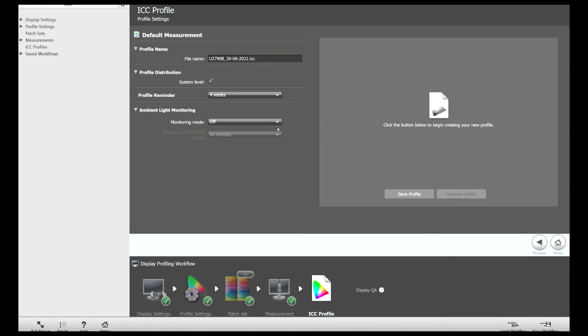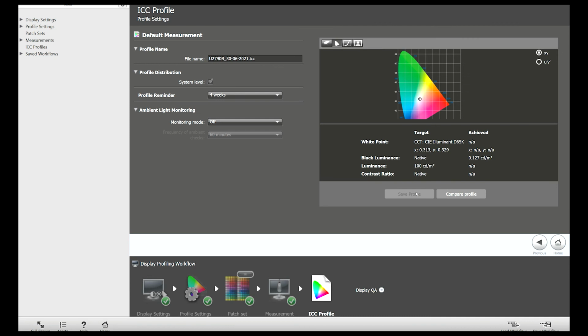And I leave the monitoring mode to off because I won't be connecting the equipment all the time, so it won't measure the ambient light monitoring. And then you hit save profile and it will generate the profile for you. So you can see the target and achieved. We are not too much off, so that way we have got the right calibration.